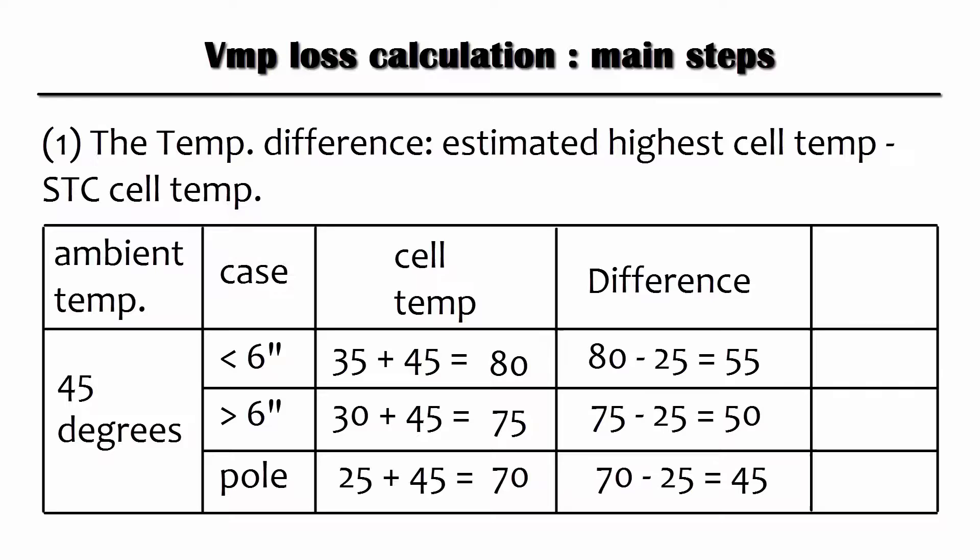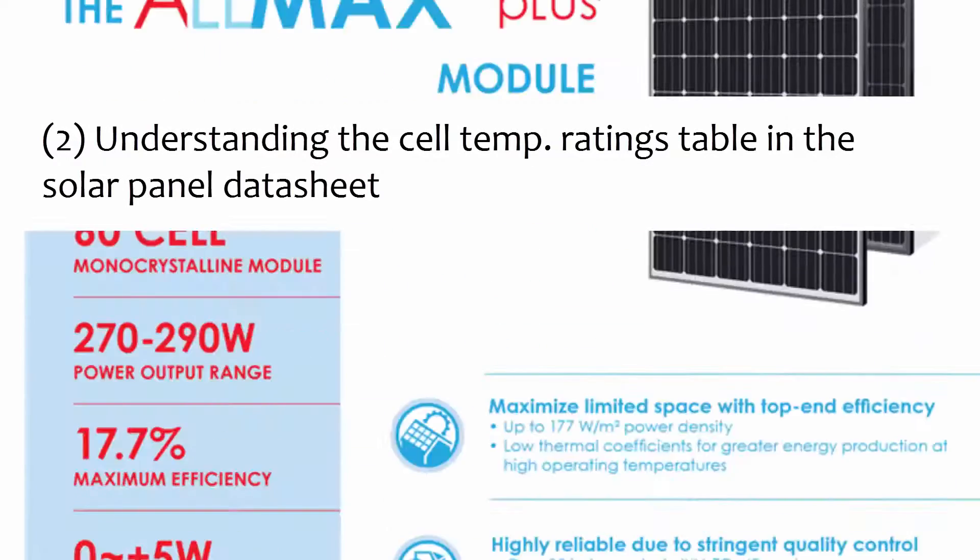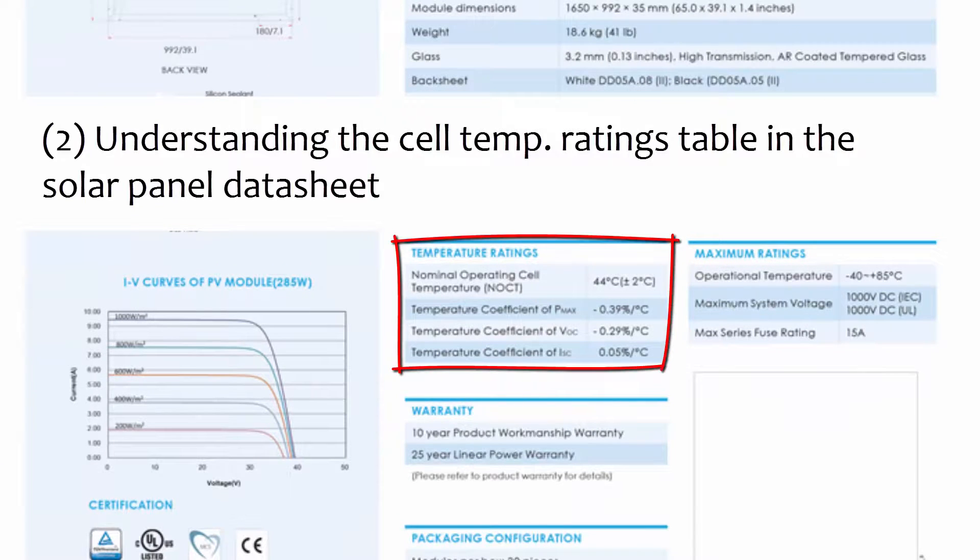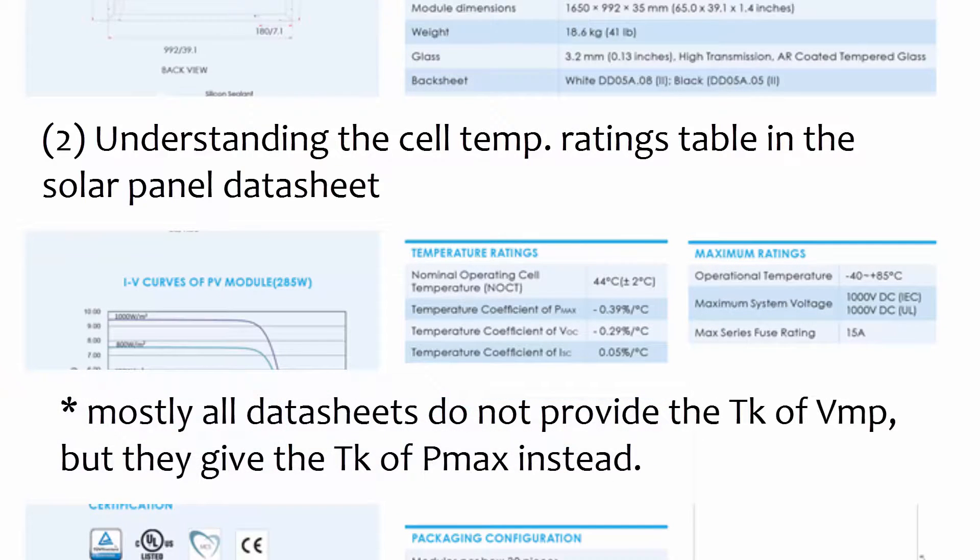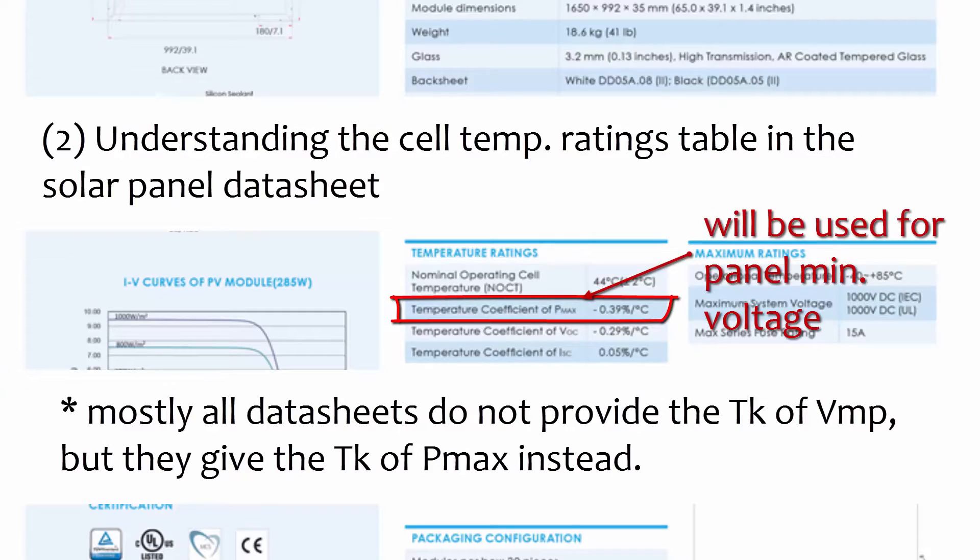The next step is understanding the temperature rating table in the solar panel datasheet. Most datasheets don't provide the temperature coefficient of the maximum power voltage, but they all give the temperature coefficient of the maximum power. That will be used for the calculation of the panel minimum voltage.